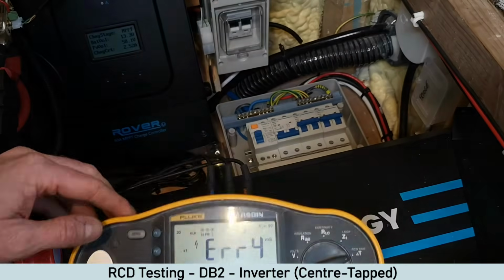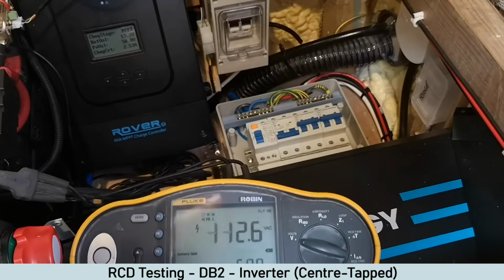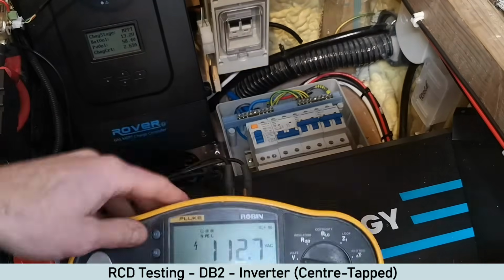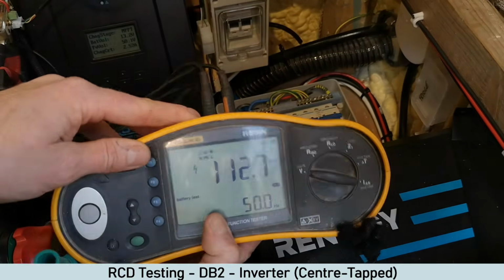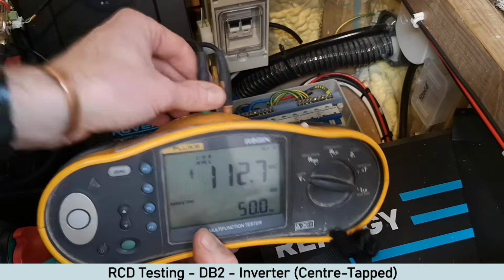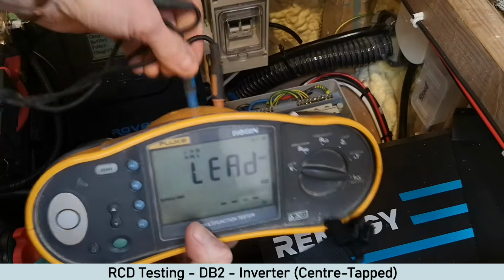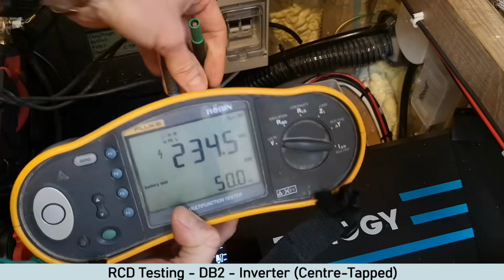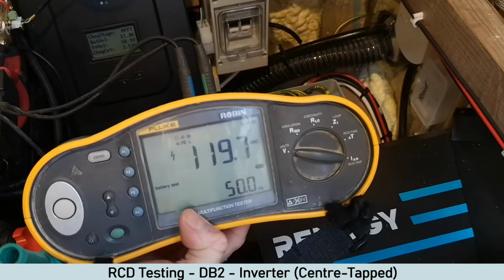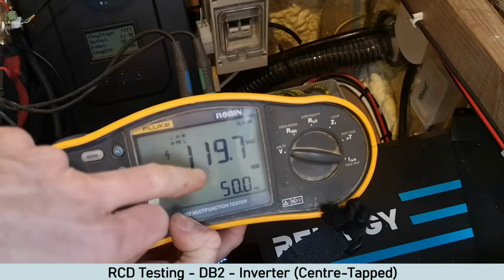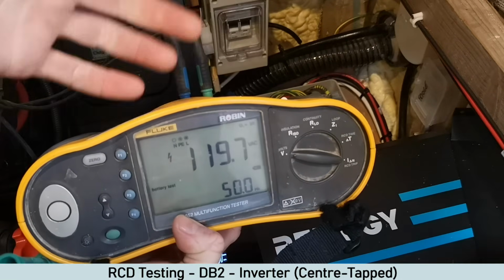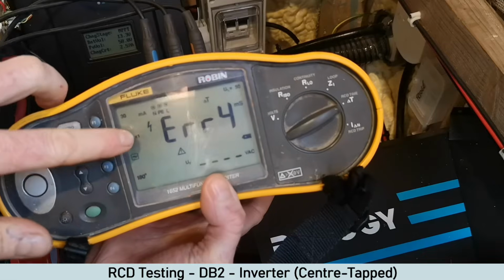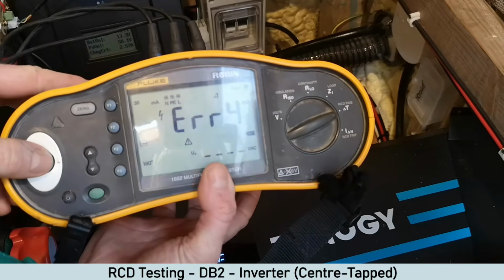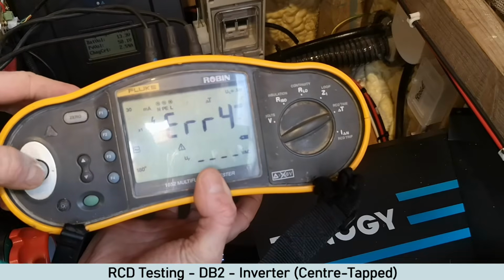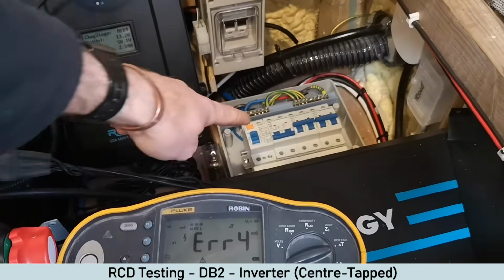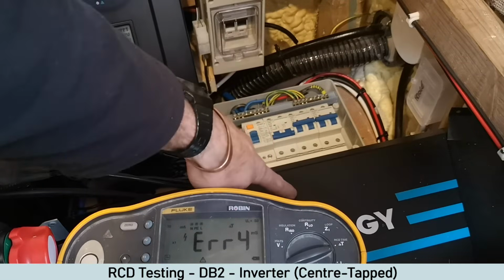Now error 4, what that means is an issue in voltage, an issue between the neutral and the earth voltage. So again, I'll show you, if I switch it to volts. Now you can see here, between live and earth, we're getting 112. If I do between live and neutral, we get 234. And if I do earth to neutral, we get 119. So that's where the issue is. It's getting a voltage between neutral and earth because it's centre tapped. So test at 30 milliamps, AC, it won't let me test because it's in error. That just shows that that RCD will not function as it should on a centre tapped inverter.